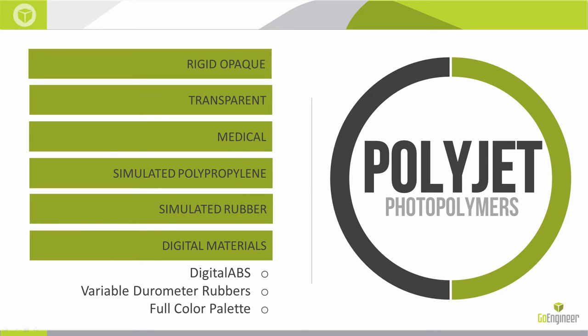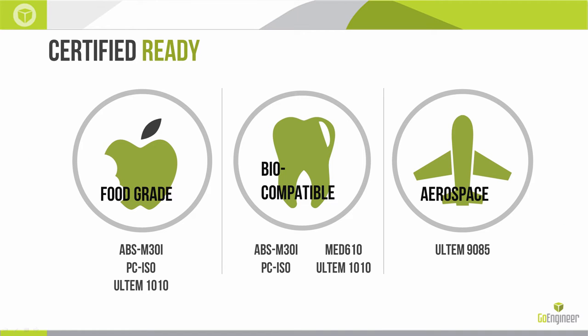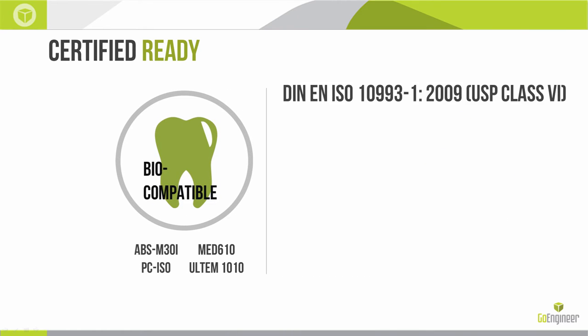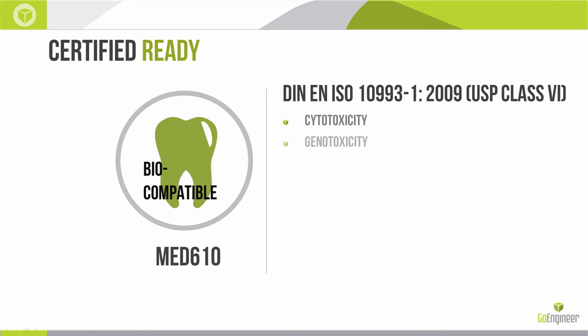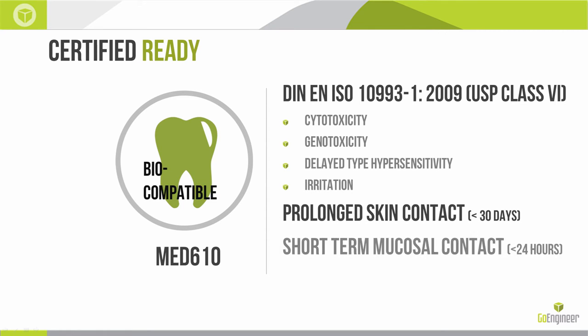Within those material sets, several groups are ready to be certified. The biocompatible category includes ABS-M30i, PC-ISO, MED-610, and ULTEM-1010, all of which are ISO-10993 certified and USP Class VI compatible. MED-610, for example, meets standards for cytotoxicity, genotoxicity, delayed-type hypersensitivity, and irritation — four standards under ISO 10993.